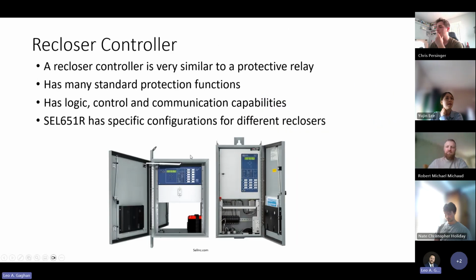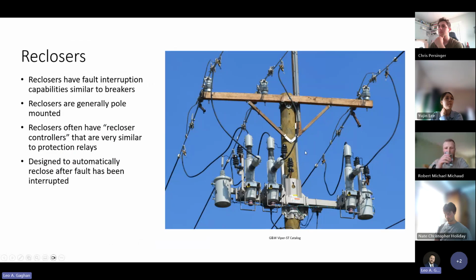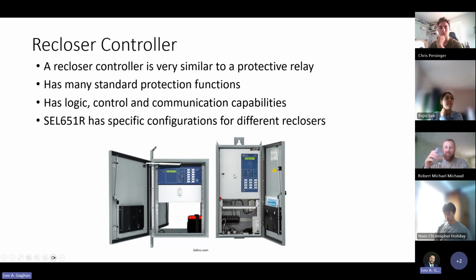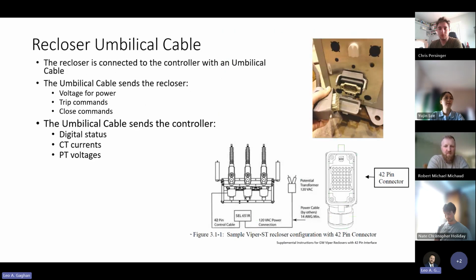So, we talked about the recloser controller. We talked about the recloser, which is obviously at the top of the pole, as we can see here. The controller is usually down at a good height for a technician to work with. So what we've got is what's called an umbilical cord. This is really what carries all of the information, power, and commands back and forth between the recloser and the recloser controller. So here is a little bit of a block diagram.